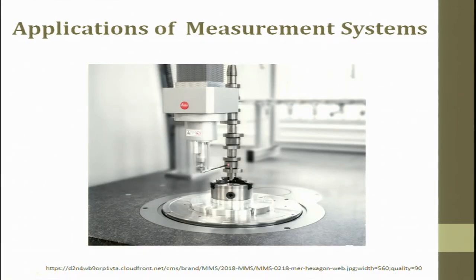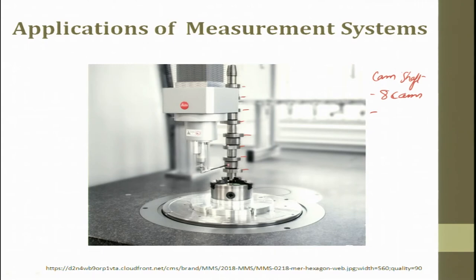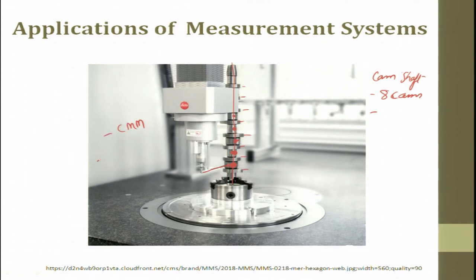Here is a camshaft with maybe 8 cams. Cams are always used for timing - something like a timer for the timely release of fluid or whatever it is. All these cams are attached to a shaft or are an integral part of a shaft. You can see these are the areas where the cam will be in contact with the housing or some place, and we are trying to measure the individual values of each cam. This is done on a CMM machine - coordinate measuring machine - where a stylus comes in contact with it and we try to get a digital display of the value at any given point of time.